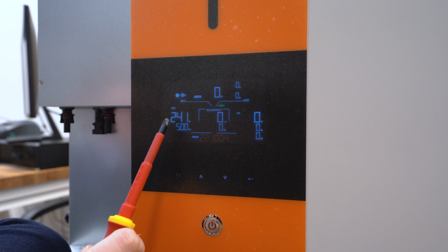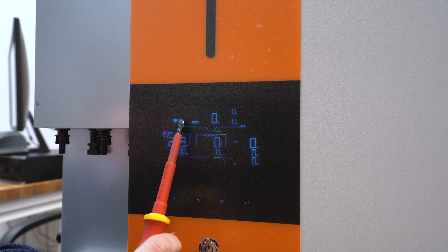On the screen we can see on this side the incoming power supply from the mains. In the middle you will see the AC output, how much energy is withdrawn by the appliances at home. From this side we can check the PV input, PV1 and PV2, the current, the voltage and the power. This signal here shows the connection to the battery. When it starts flashing, it means that the battery is successfully paired with the inverter.